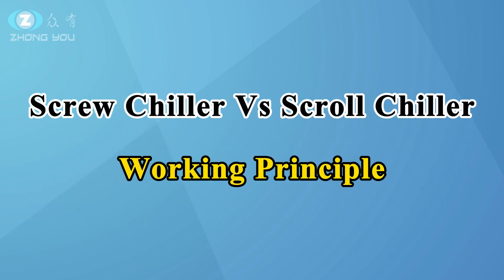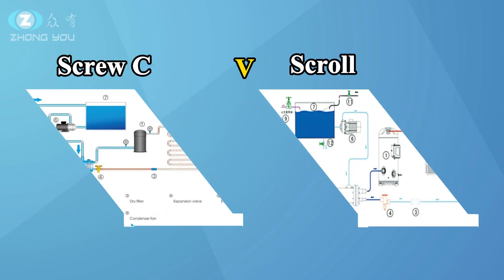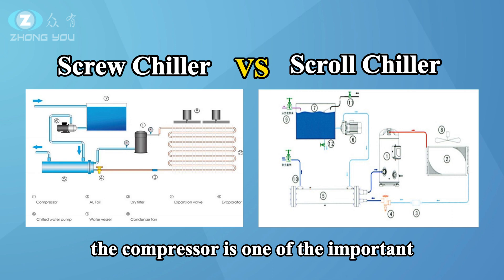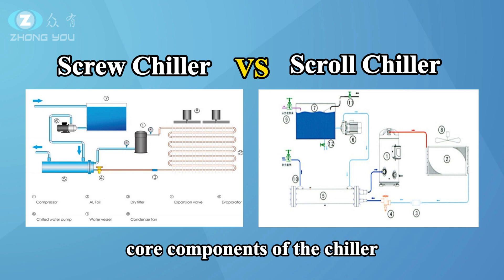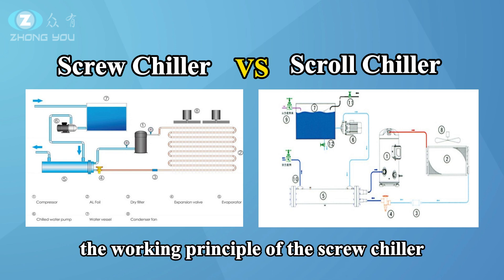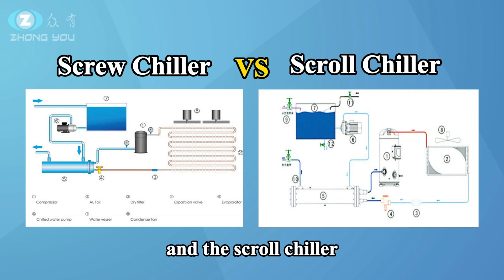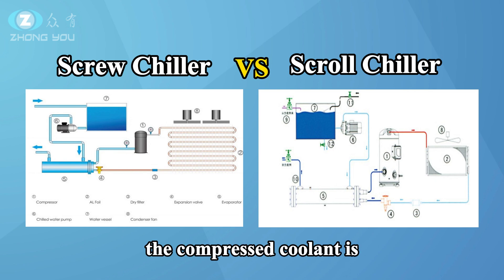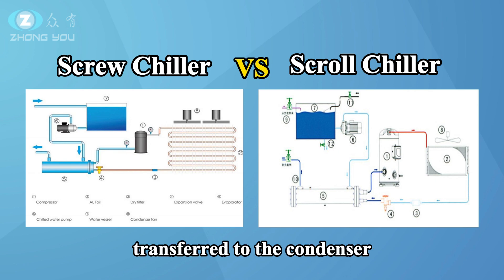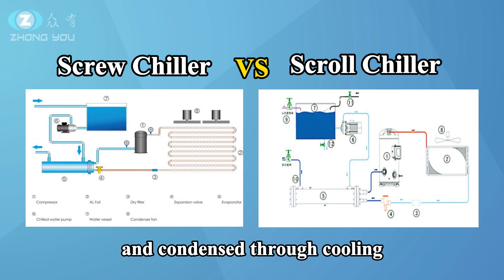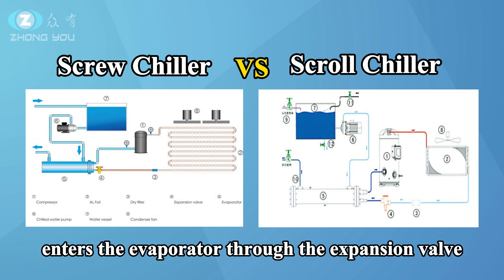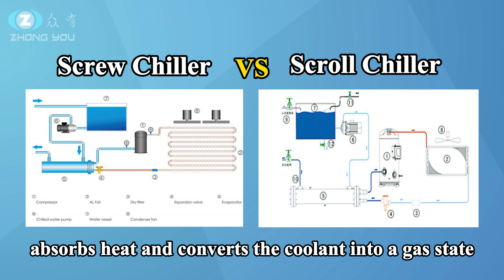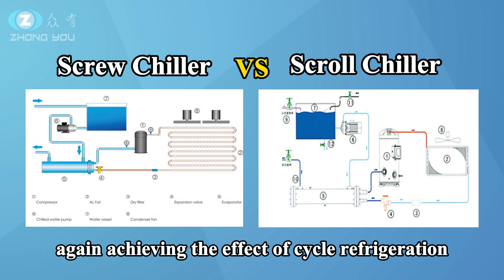Screw chiller vs. Scroll chiller — Working Principle. The compressor is one of the important core components of the chiller. The working principle of both the screw chiller and the scroll chiller is to use the compressor to compress the coolant. The compressed coolant is transferred to the condenser and condensed into a liquid state, then enters the evaporator through the expansion valve, absorbs heat, and converts the coolant into a gas state again, achieving the effect of cycle refrigeration.